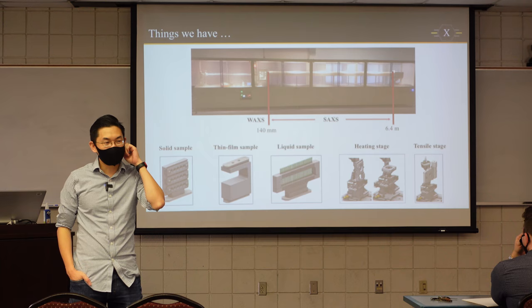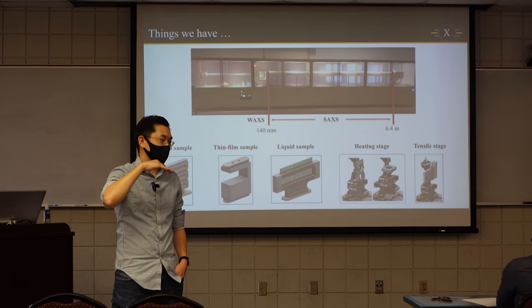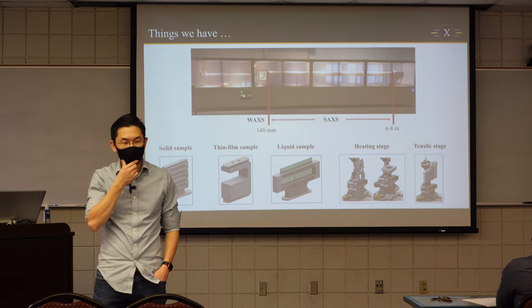They have the controller, so you can control the temperature profile. You can control heating rate, cooling rate, and the high temperature depends on the setup, but it can go as high as 600 degrees Celsius, okay? We have a setup here. We have commonly used them to measure polymer degree of crystallinity at different temperatures.